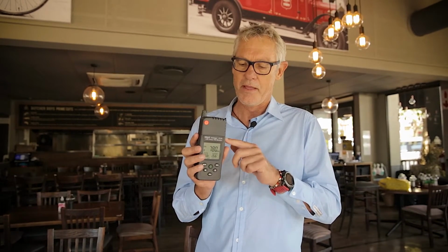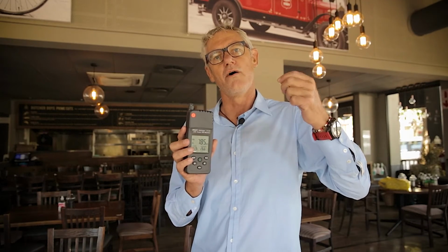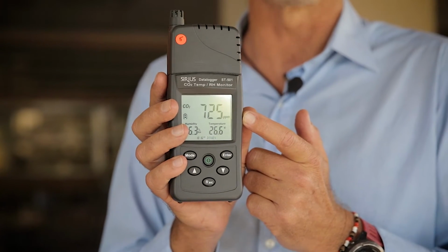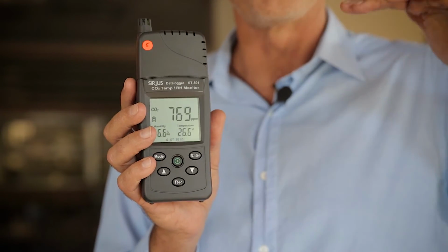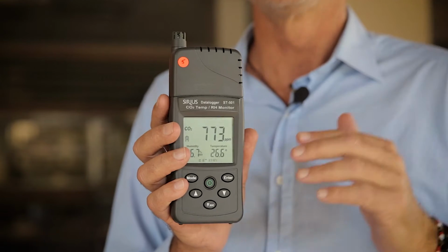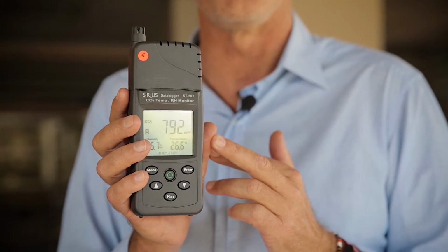And then there's a strong correlation between carbon dioxide concentrations and the effectiveness of the ventilation systems inside that occupied space. Obviously, the poorer the ventilation system, the higher the carbon dioxide concentration, the higher the correlation or potential for that environment to contain airborne viruses and other airborne pathogens. So anything below 800 is considered excellent. Then as you go above 800, it graduates from excellent to good and then good to poor. So anything over about 1,000 parts per million, we start saying that it's poor ventilation inside that occupied space.